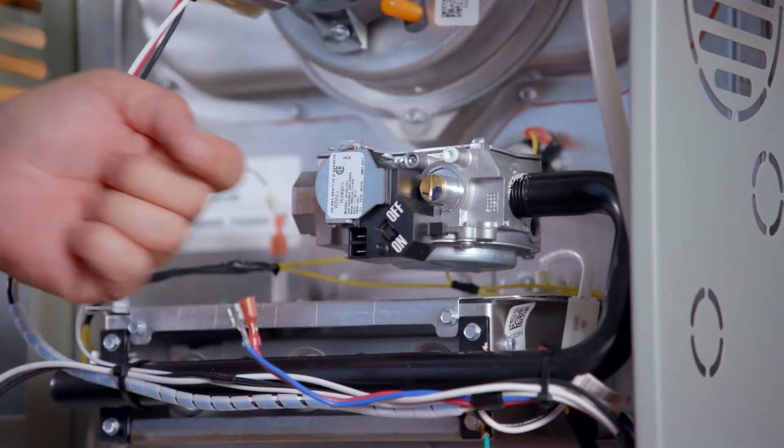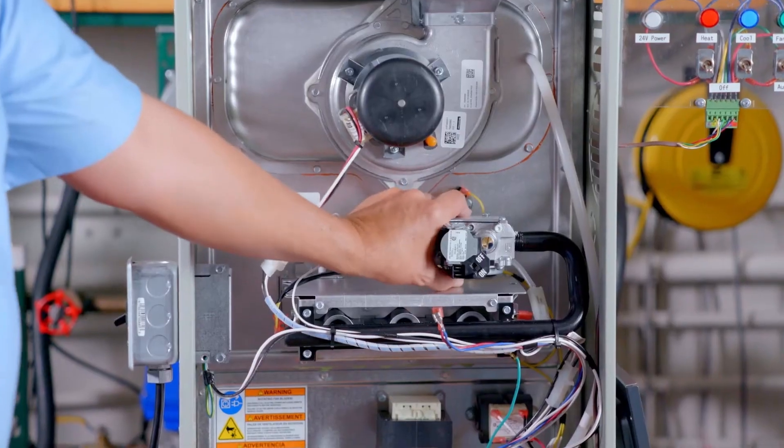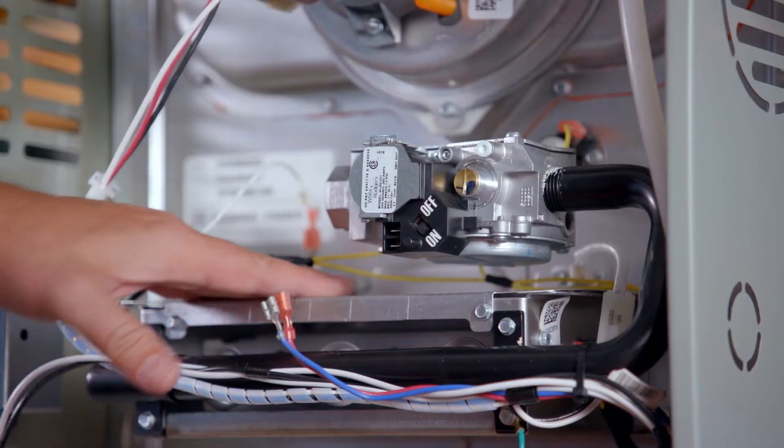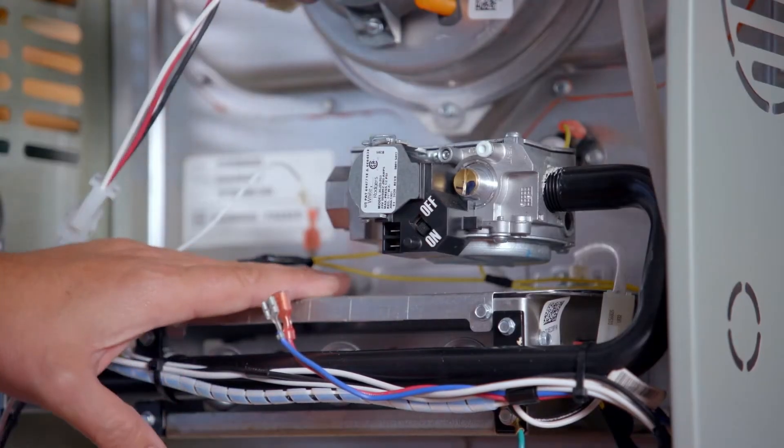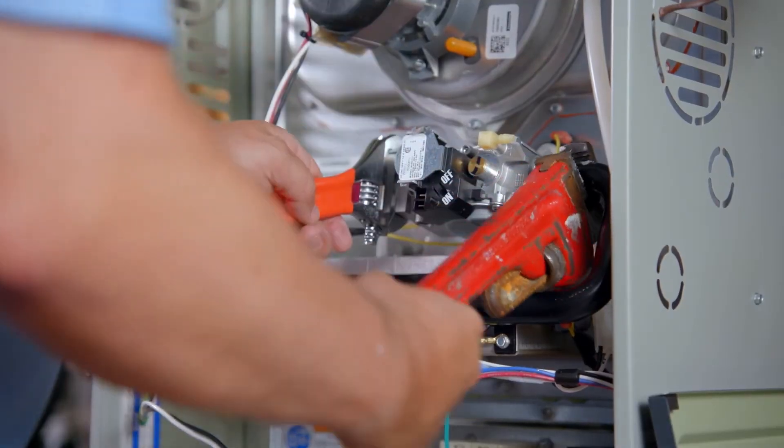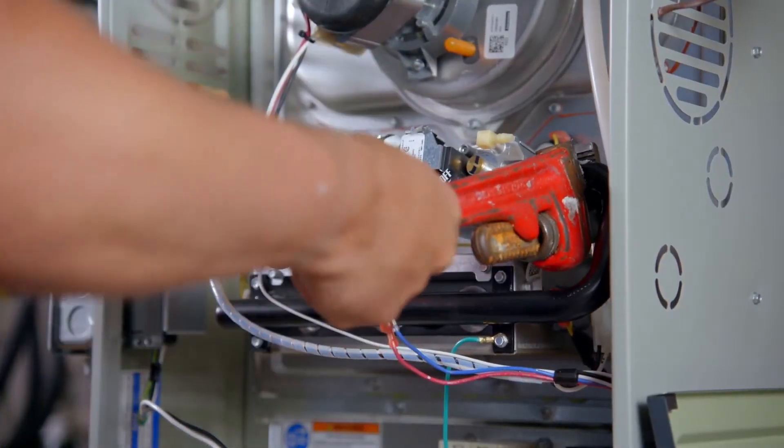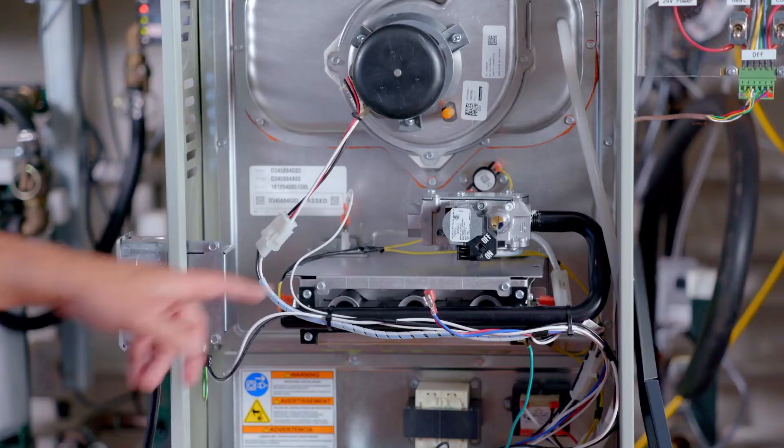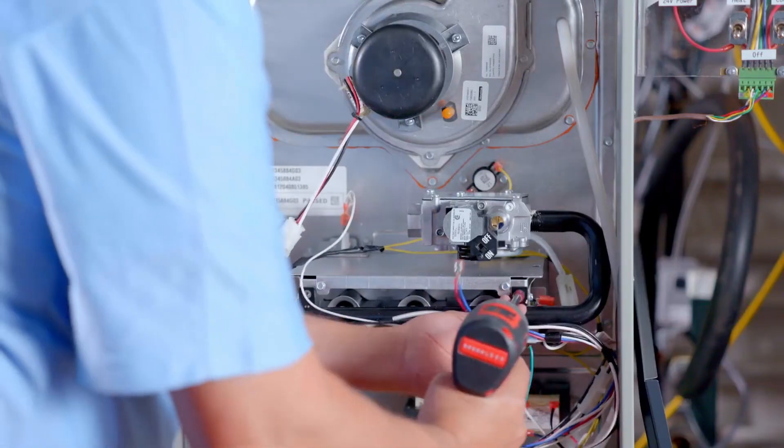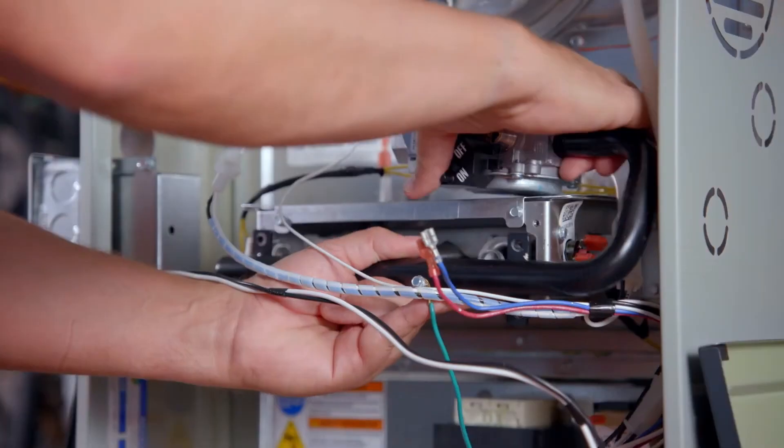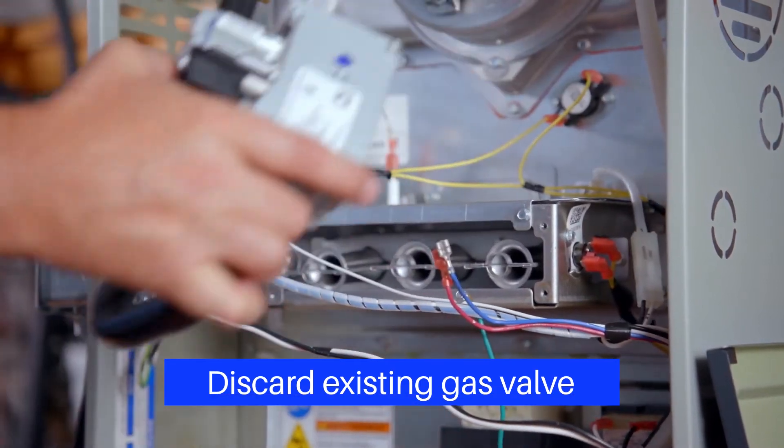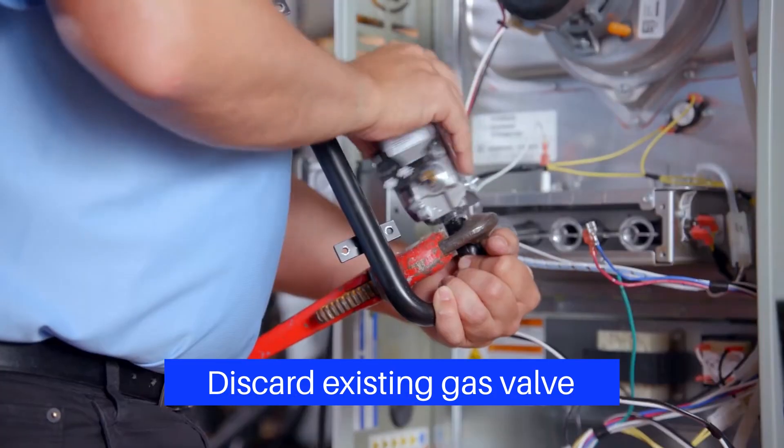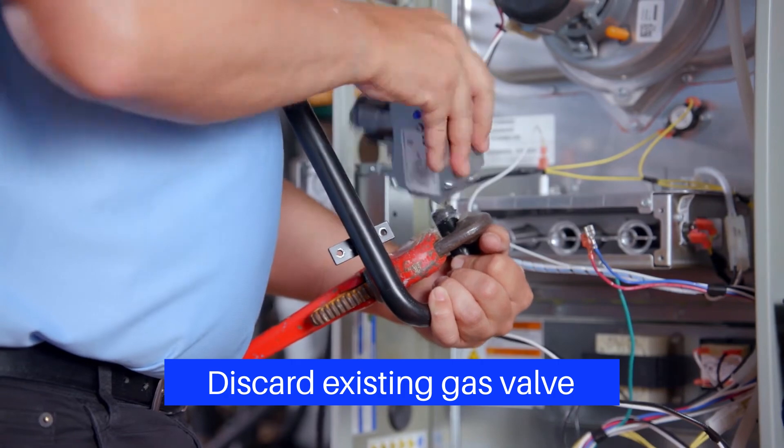Take note of the old valve orientation before removing. Determine if the existing valve can be spun off while in place. Use caution not to bend the manifold brackets by securing a wrench on the manifold prior to removing the existing valve. In some applications, the gas manifold must be removed. Remove the manifold bracket screws, allowing the valve and manifold to be removed together. The existing valve can now be removed and discarded.